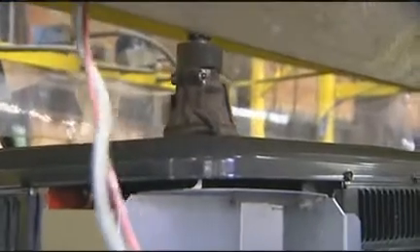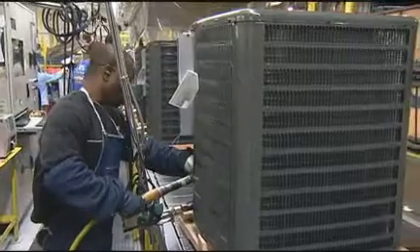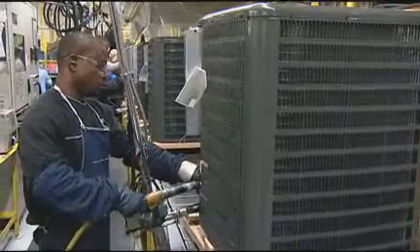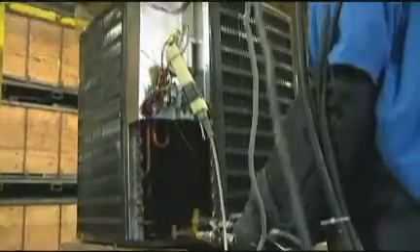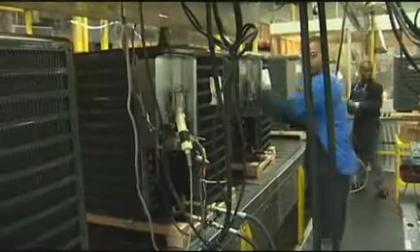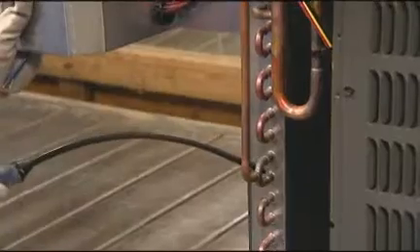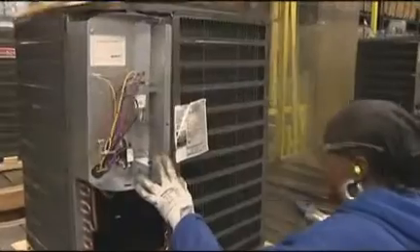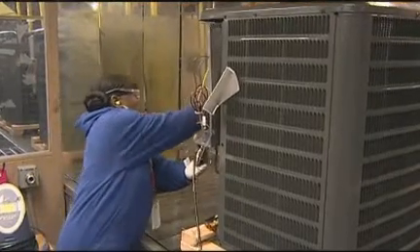If you look on the units, you have an accelerometer where it measures the vibration on the unit. So while the unit is running, it makes sure we don't have any loose components, something didn't get tightened. We do a gross leak check on a braze line. We do a pressure decay, which is a gross leak check. Then after it passes those 200% check inspection, it goes through that booth right over there, and it checks for the fine little leaks. Now you've seen, Mark, all of our processes, all of the systems, and now this is why we invite our potential customers to come and see us and put us against any of the competitors or the product out there.